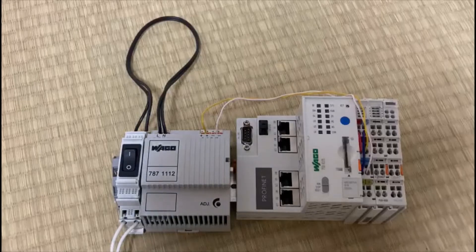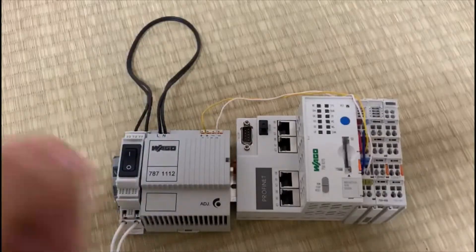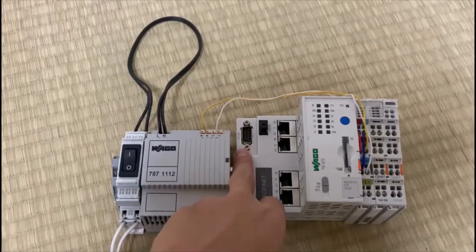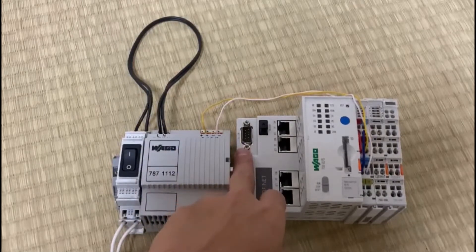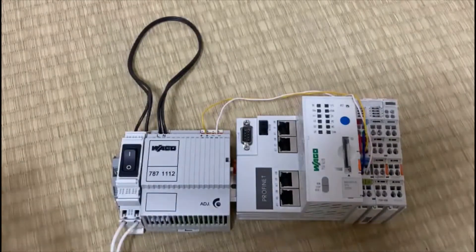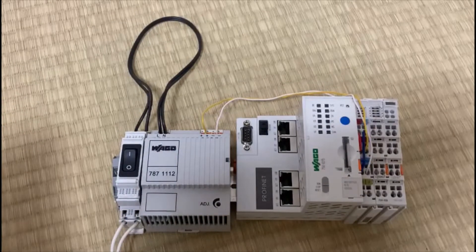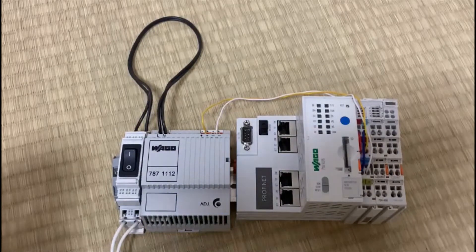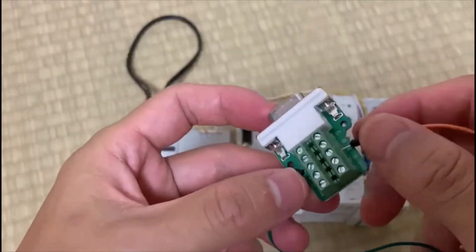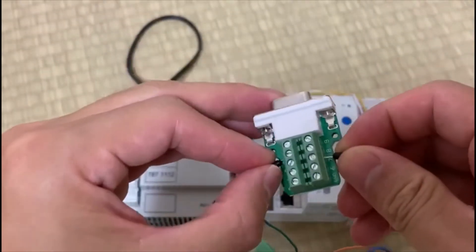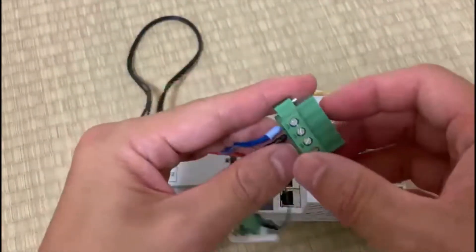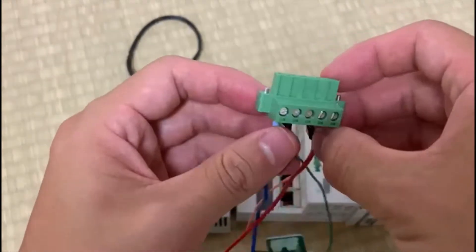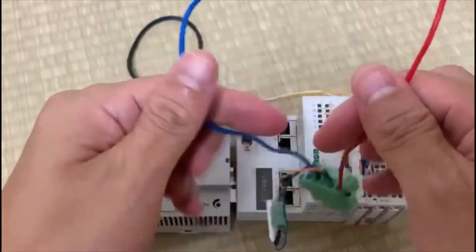In this part, I will show you how to wire the WAGO PLC to the CANopen sensor. Don't worry, it's very easy. We will use this X4 CAN as the CANopen master interface. Refer to the manual, pin 7 is CAN-H and pin 2 is CAN-L. You can buy a 9-pin female port and connect pin 7 and pin 2. But I will use these connectors with a terminal to wire into each pin. I use pin 7 and pin 2, wire the cable in here and connect to the other five terminal connectors. These connectors, here is CAN-H signal, CAN-L signal and 24V supply for the sensors.